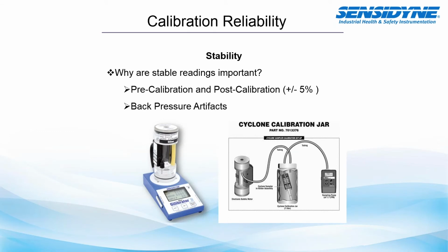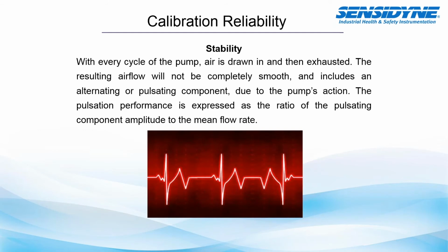So why are stable readings important? Obviously, as I just mentioned, we want to make sure that our pre-calibration and post-calibrations are within that plus or minus 5%, and also to make sure that there's no back pressure artifacts, which is a bias created by the calibrator itself. So this is a case where stability comes into play.